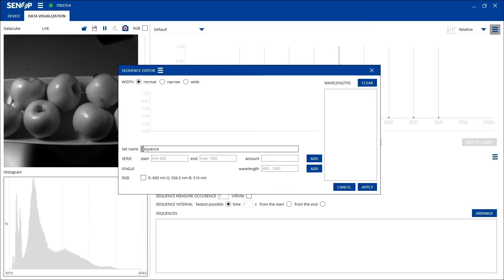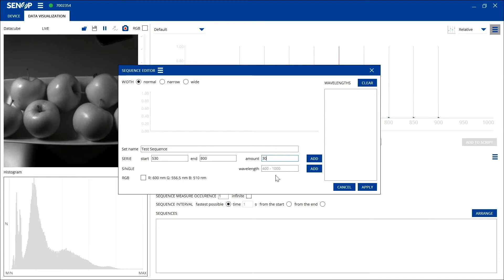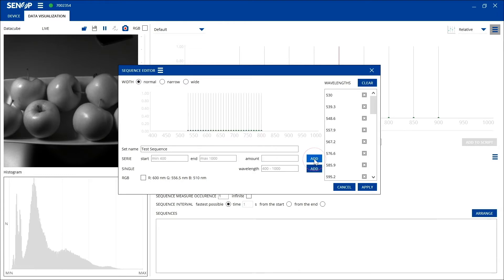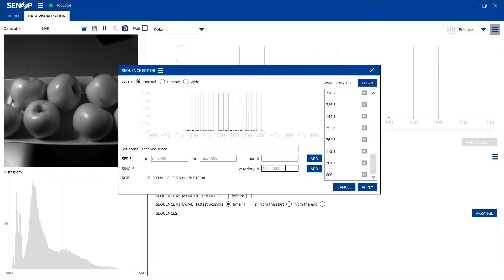First create a name for your sequence. The next step is to define what wavelengths you want to image. Then add the number of bands you want to take. Click the add button and you can see your wavelengths in the right hand side. You can also erase specific bands by using the X button on the right hand side and add new specific bands by using the wavelength field below the band selection.